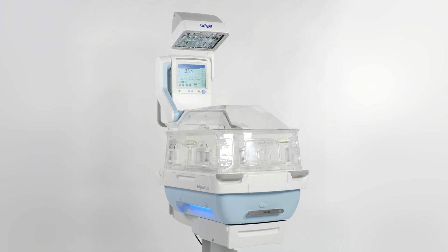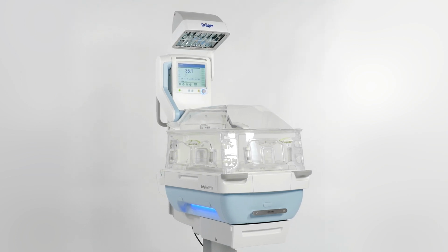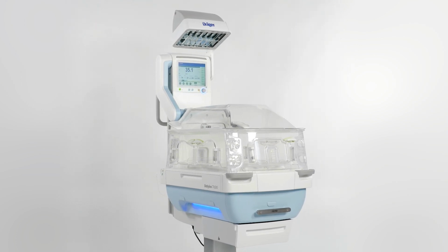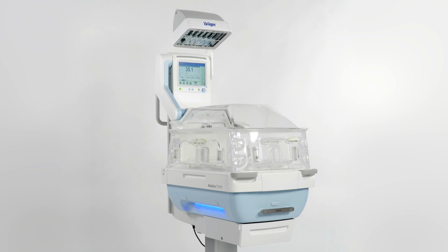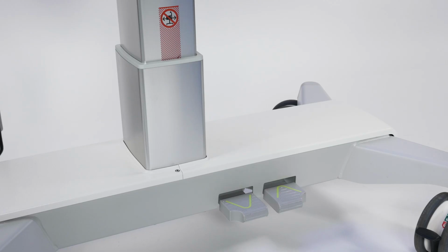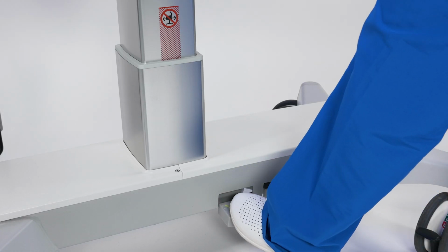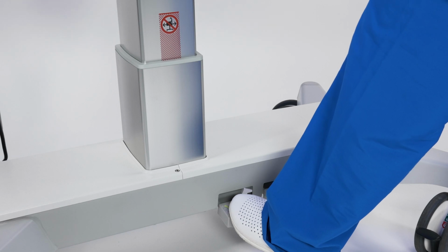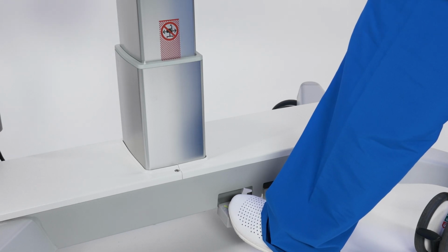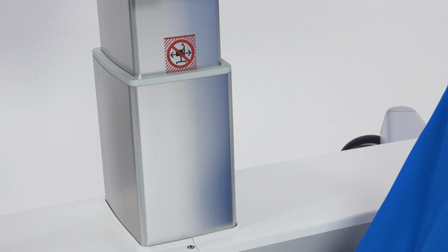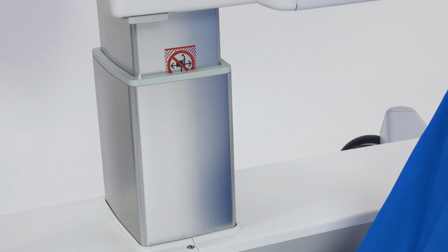To prepare the transport, close the hood and make sure the temperature and humidity inside the incubator are sufficient for the patient being transported. Make sure the device is set to the correct height for transport. This will prevent it from tipping over. Use the foot pedals to adjust the height until the red hood label is no longer visible on the column.